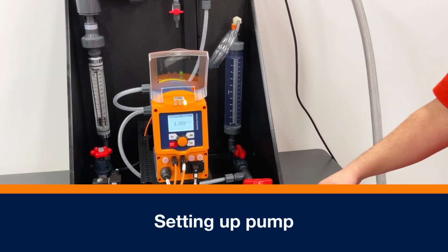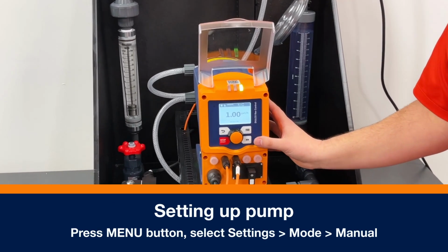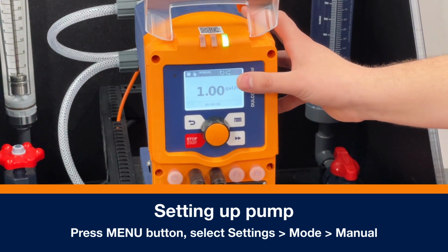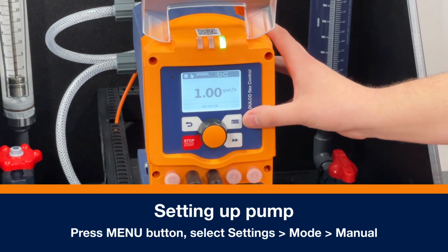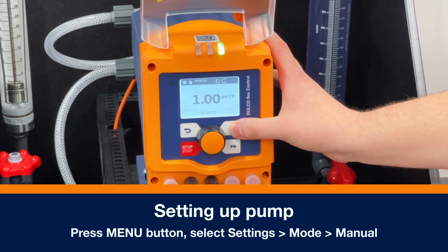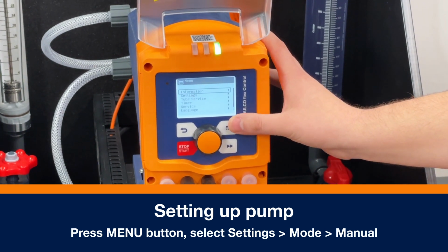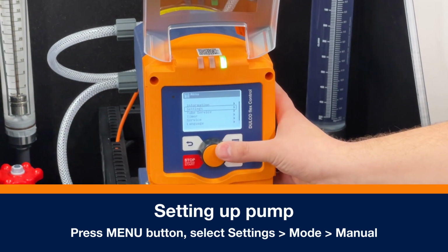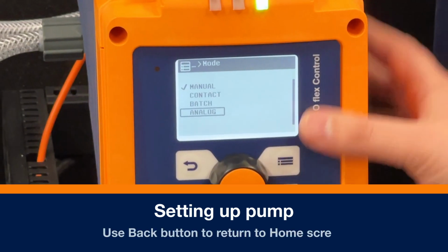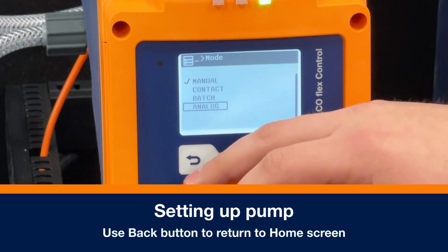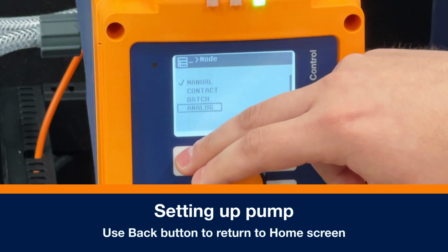Next, we're going to talk about setting up the pump. From the pump here, you can see that we have it set in manual mode right now. In order to change that, we come over, we press the menu button. We come down to settings and mode. For the rest of this video, we're going to stay in manual to show the function of the unit.